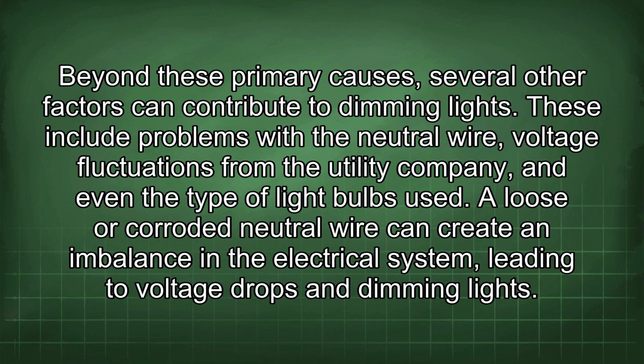Beyond these primary causes, several other factors can contribute to dimming lights. These include problems with the neutral wire, voltage fluctuations from the utility company, and even the type of light bulbs used. A loose or corroded neutral wire can create an imbalance in the electrical system, leading to voltage drops and dimming lights.